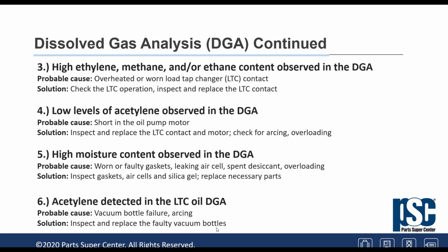Item 4 says it could be an LTC, a load tap changer. We have two types of tap changer. One has an arcing tap changer, the other has a vacuum tap changer. With the vacuum tap changer there shouldn't be any arcing, but with the arcing type, there should be arcing because that's the way it's designed. Sometimes there's a migration from the LTC compartment to the main tank, and there we can find some minute part of acetylene in the main tank. So that's what we do: we open up the tap changer, we drain the oil, of course, and then we check the arcing and so forth. And we keep an eye on the main tank too.